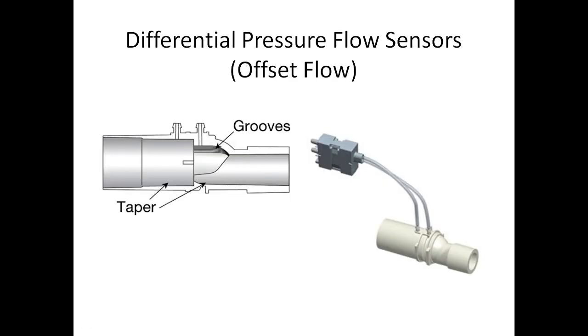Differential pressure with offset flow. Offset flow also uses Bernoulli's principle. Interestingly enough, there's a taper between the two sections of the tube, and that turbulent airflow in the middle actually creates the obstruction. Normally this type of flow sensor has no moving parts, which makes it extremely reliable. However, they had a problem with moisture. So what they did is they created little grooves in the roof of the curvature, and those grooves help dissuade moisture from condensating and building up into large droplets. The large droplets could occlude your pressure tubules right here, and that would create incorrect readings.